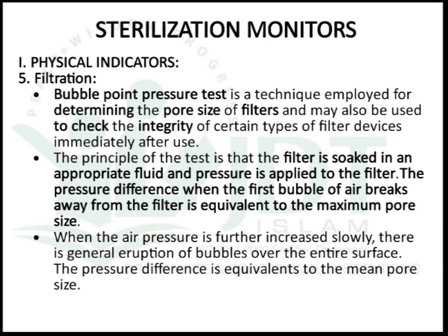Physical indicators in filtration are monitored by performing a bubble point pressure test, which determines the pore size of a filter and checks the integrity of certain filter devices after use. The filter is soaked in an appropriate fluid, and when pressure is applied the pressure difference at which the first bubble of air breaks away is equivalent to the maximum pore size. When air pressure is further increased slowly, general eruption of bubbles over the entire surface gives the pressure difference equivalent to the mean pore size.